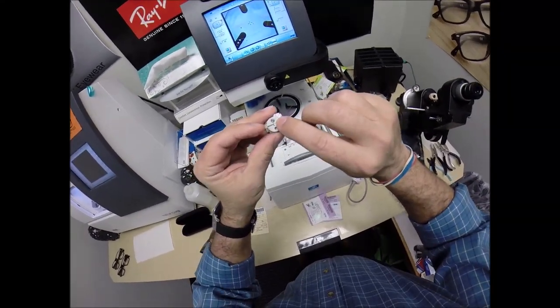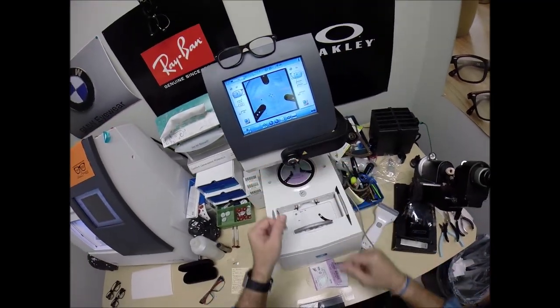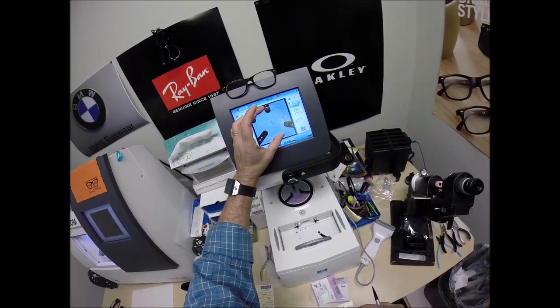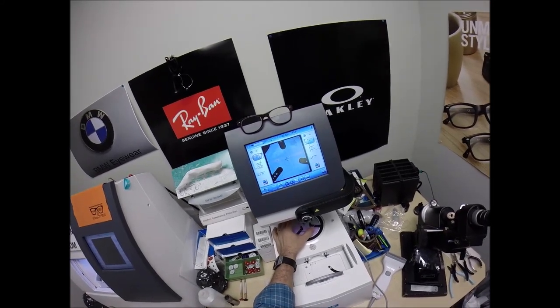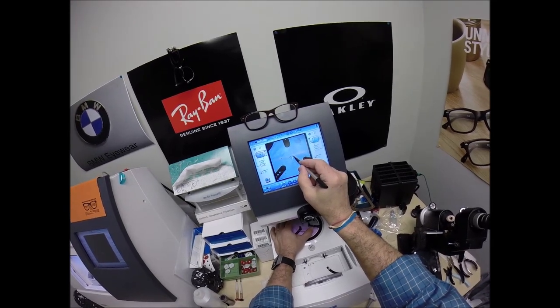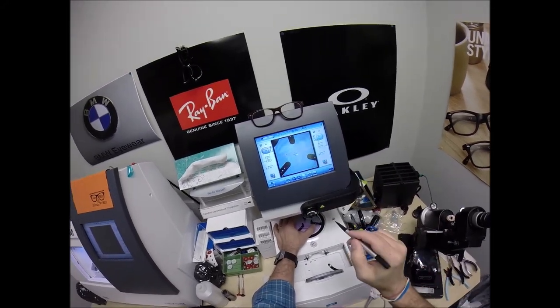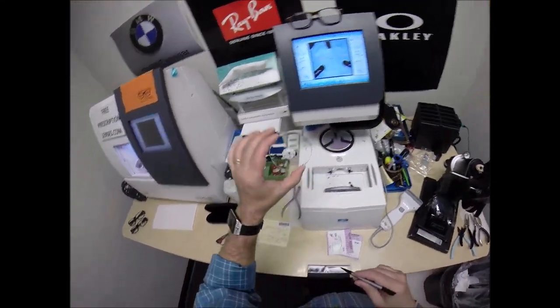On the back, that silver button is a magnet. It's going to do its job twice. The first time, it's going to attach itself to another magnet there in the arm. And the reason why I put those 3 dots on there, it tells me that the lens is oriented in there just perfectly because of your astigmatism correction. It can only go in one way. I'm going to line everything up. That black dot is your optical center. It's going to sit in front of your pupil. These other 2 dots tell me it's oriented in there just perfectly. I want to see the size of the lens. That looks good. Hit the button. The arm's going to come down, place the block onto the right lens.